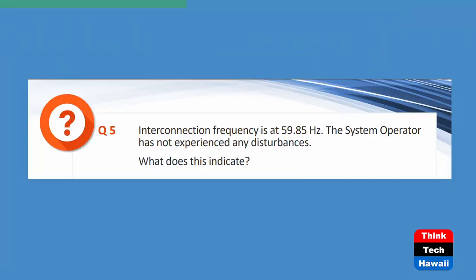The last question we have on here is: interconnection frequency is at 59.85 hertz. The system operator has not experienced any disturbances. What does this indicate? Well, if you don't have a problem in your system and your system is showing a low frequency, there's a good chance there's something happening outside your system. You haven't lost generators. You don't have a voltage collapse. Your ACE is still fine, right? You're meeting all your load. But that means something has happened outside your system.